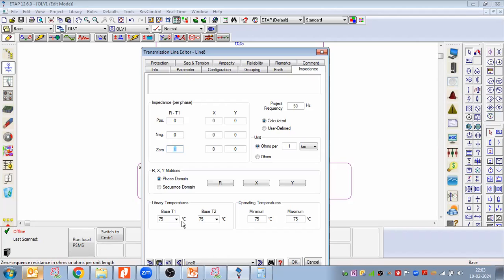If you see here, base T1 and base T2 refer to resistance at a given temperature, since resistance changes with temperature. I'm putting 75 degrees Celsius here. So I check the conductor's technical data sheet for the specified temperature and put the value here accordingly.